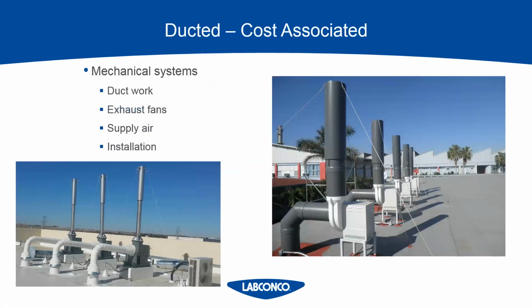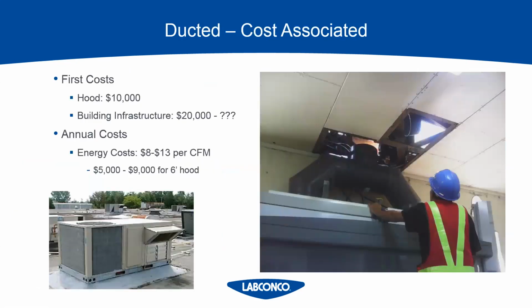So the typical costs associated with a ducted system, of course, have to do with the duct and ducting that hood out. So that is the actual equipment and energy usage costs. The upfront costs are the hood, the ductwork, the exhaust fan, and the extra tonnage required to air condition the air that you'll be sending outside, because you have to add more air into the space to duct it outside. And then the installation, which could mean putting holes in your walls and a roof, and all of that can really be costly.